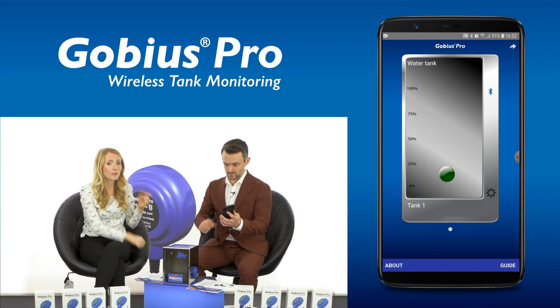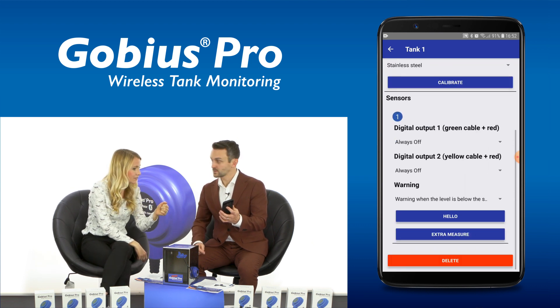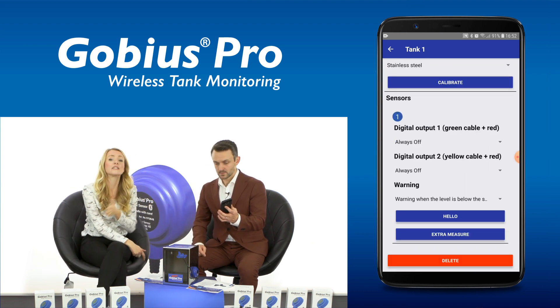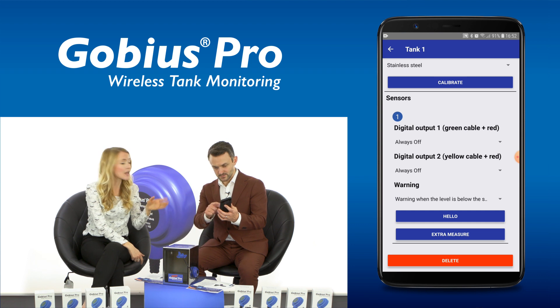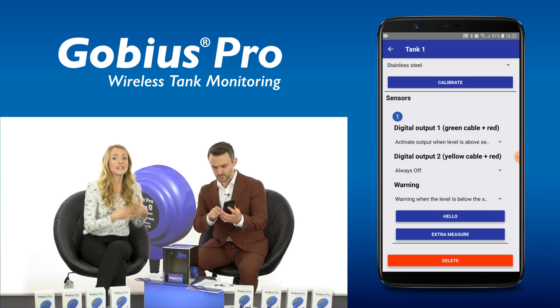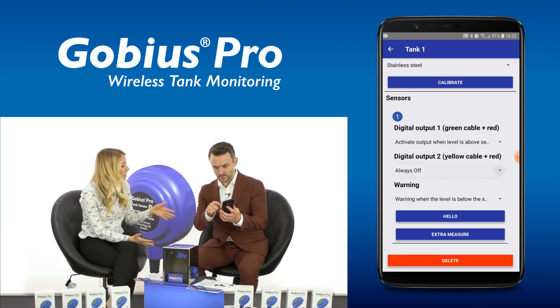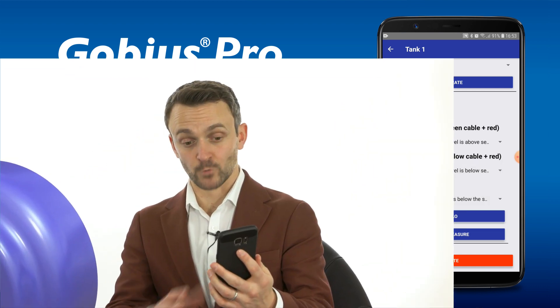Can we program the Gobius Pro so it shows the green LED light when the level is above the sensor and a red light when it's below? Let's do that. Click the cog from the monitor screen, then select Edit, then scroll down to the sensors section. Now you can see Digital Output 1 and 2. Select Digital Output 1 and choose activate output when level is above the sensor. Now do the same for Digital Output 2, but this time select activate output when level is below the sensor. All done.